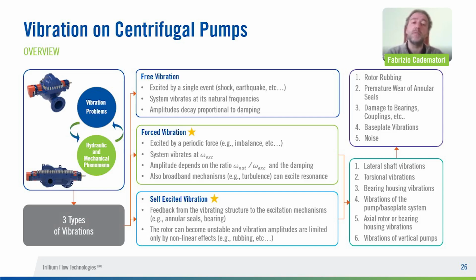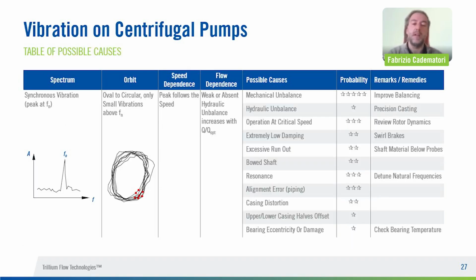Self-excited vibration occurs when there is a feedback between the vibrating structure and the excitation mechanism. A typical example is the force generated in sleeve bearings and annular seals. If damping is sufficiently low, a self-excited vibration is created. While free vibrations are not really significant in pump operation, forced and self-excited vibrations frequently cause problems, which can be classified as lateral vibration measured by proximity probes, or torsional vibration due to unsteady torque from the motor, and so on. It's very important to fix issues related to vertical pumps, since in this type of pump, journal bearings have no defined loading, so they are prone to instabilities. Next slide, please.